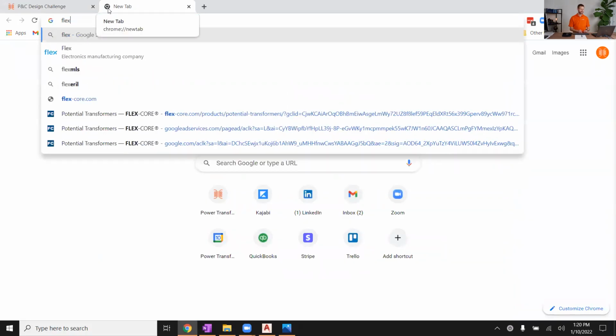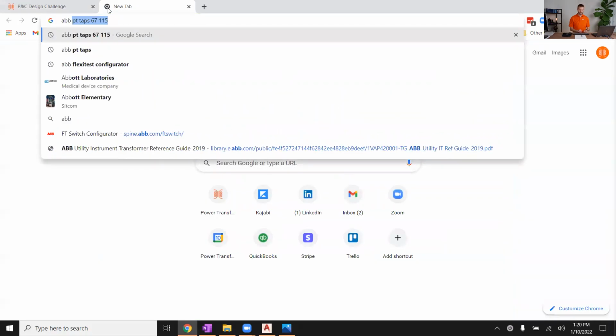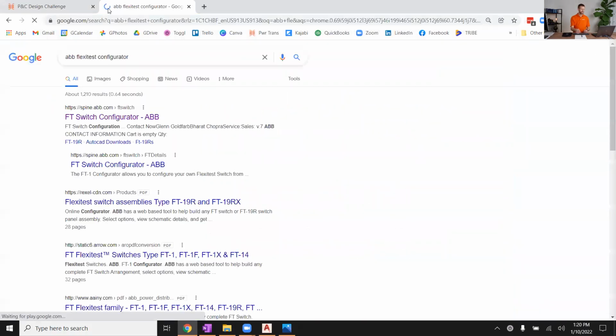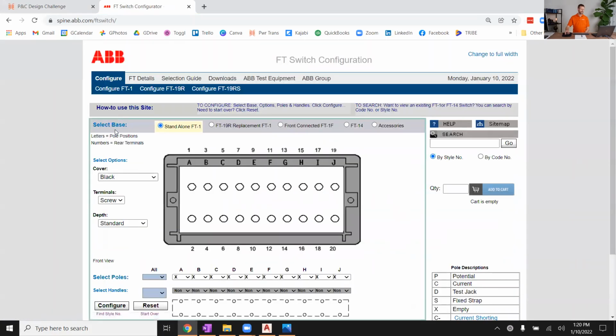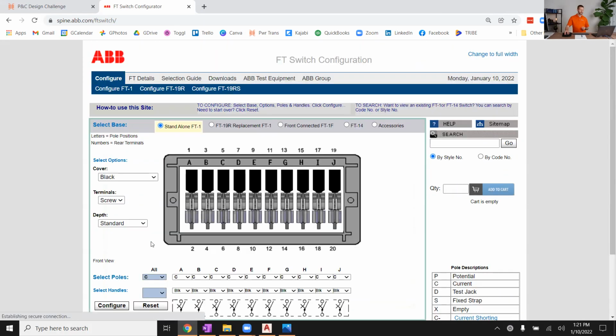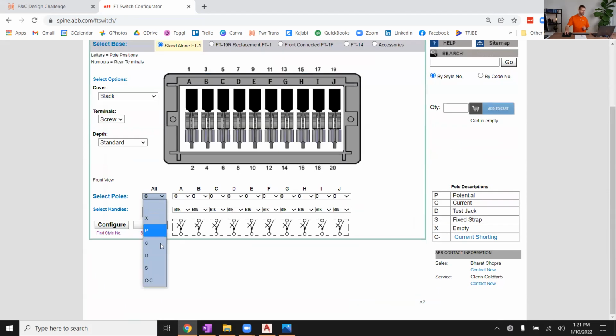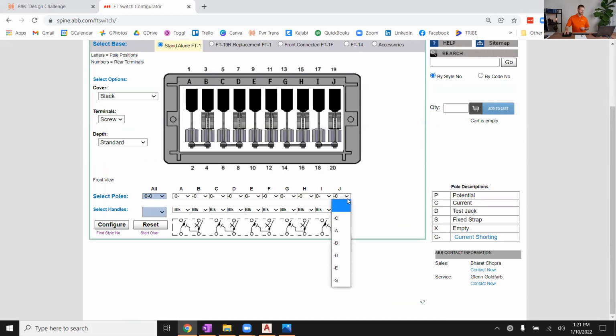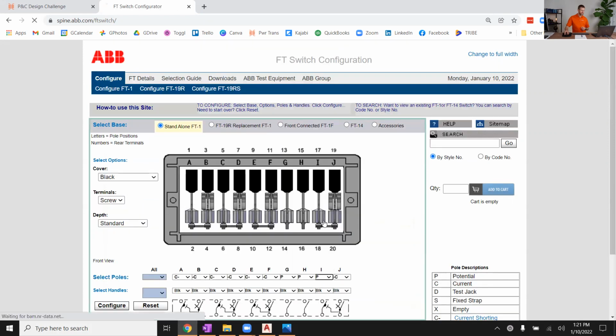The best way I can describe it for you is with an ABB demonstration here. Flexi test configurator is what I usually type into Google. FT switches. And this is actually a test switch block. It has 10 different switches that you can configure on here, labeled alphabetically A through J. For starters, I'm going to make them all current test switches, shorting current test switches. But then I'm going to change the last 4 of them to potentials instead of currents. Let's see here. P, there we go. That's what I wanted to see. P and P, but P is for potential.